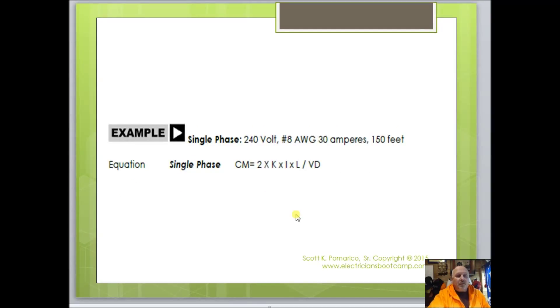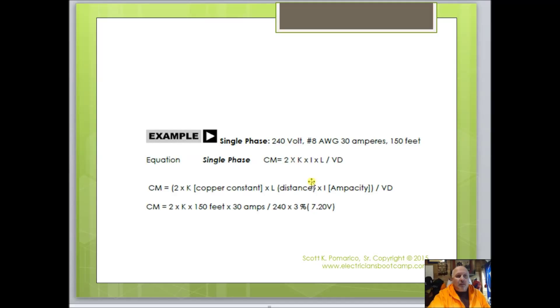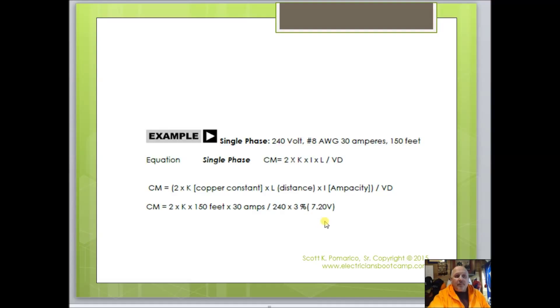Here's another version: 240-volt, number 8, 30 amps, 150 feet away — this time we're looking for circular mils. We take 240 times three percent, which gives 7.20 volts. Then the formula is CM = 2 × K (12.9) × L (150) × I (30), divided by 7.20. Divide the top number by 7.20 to get your answer. If you have questions, feel free to email me.